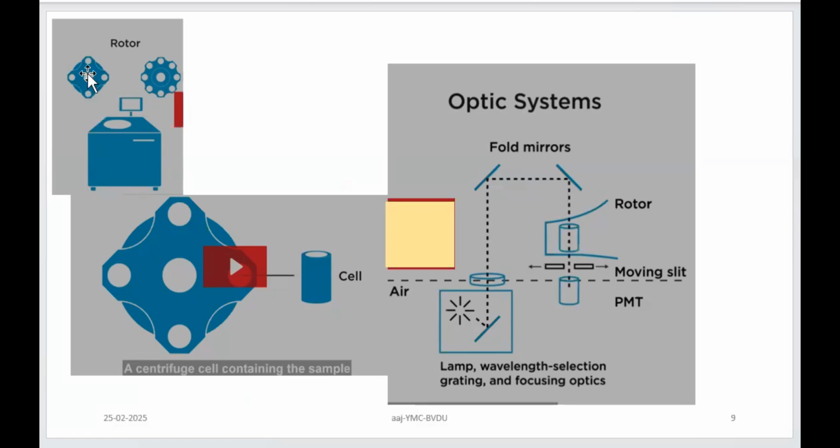The central hole is not the chamber, but it is the central shaft of the centrifuge. So in the center also you are seeing one circle that represents the shaft, right? But these four are the cells. So here a four cell rotor is there. In this case 2, 4, 6, 8, an 8 cell rotor is there. Like that you have different designs available.